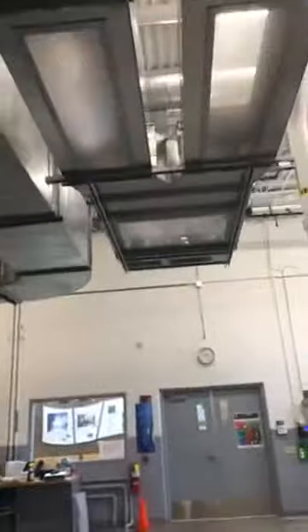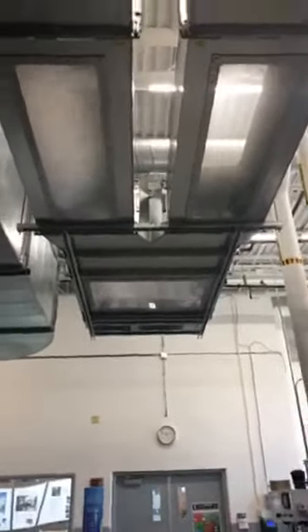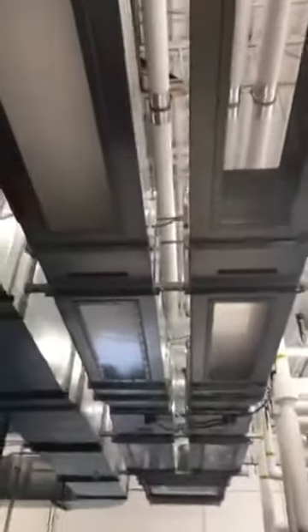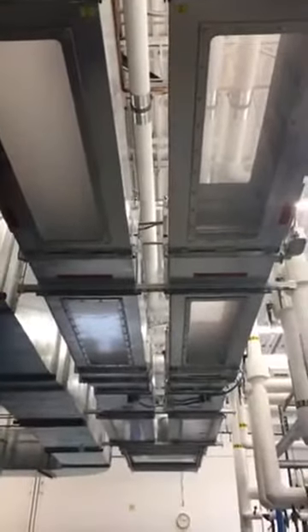Now what Paul's doing is he's turning down the exhaust fan, okay? Go ahead and open up that alarm fire smoke damper. To really drive the point home, the small duct on the side over here now is going to demonstrate, look how small that duct is and how quickly the smoke can start filling the space. So this would be an outlet going to a hospital room, an office space, somebody's apartment, condo, you name it. It doesn't take much time at all, and you can see that we can fill this space. This is a very large room. I can totally fill this room with smoke in a matter of minutes.